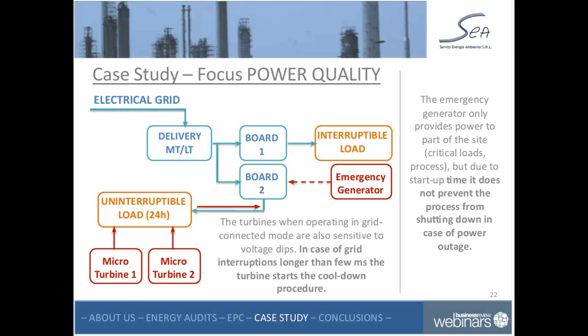So what happens is that in case of short interruptions, in the order of a few milliseconds, the microturbines themselves shut down and start the cooling procedure. They cool down and you have to switch them on again. So the issue remains, and it might even get worse with the microturbines. So we need to find a solution for that.